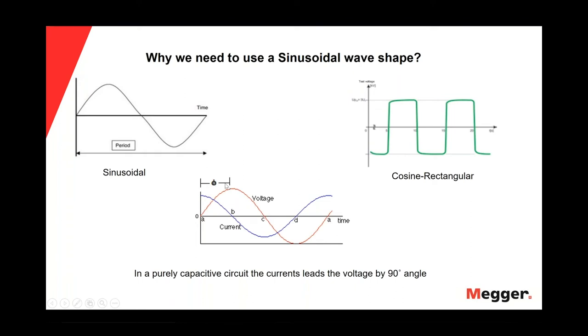So this is very important to measure the tan delta. And the problem is that if we try to use a cosine rectangular wave shape to measure the tan delta, then we don't have a phase reference between current and voltage, because in the cosine rectangular wave shape, we will have these DC plateaus or DC components. And that's the problem, because then we don't have a phase reference between the current and the voltage. That is the reason we use the sine wave shape to measure the tan delta.